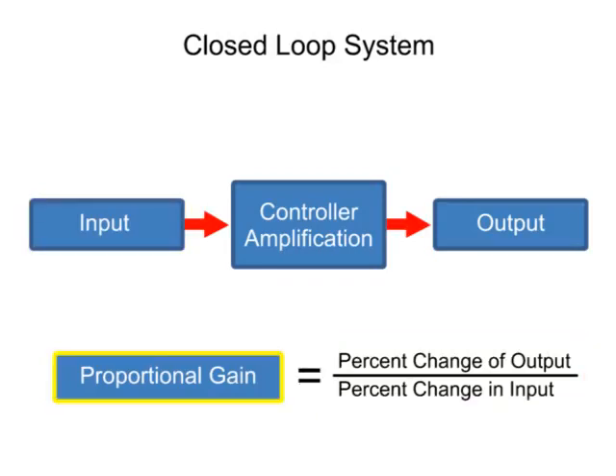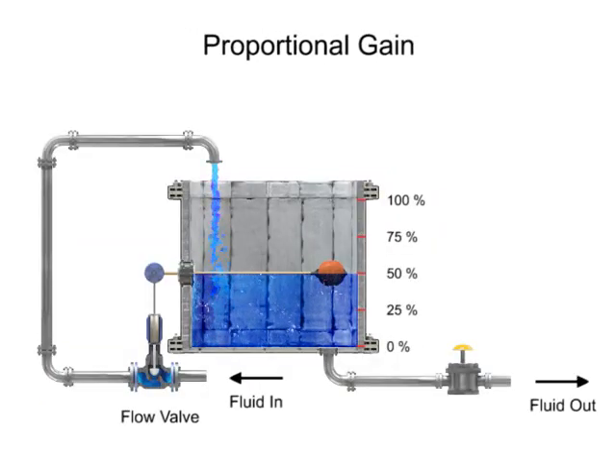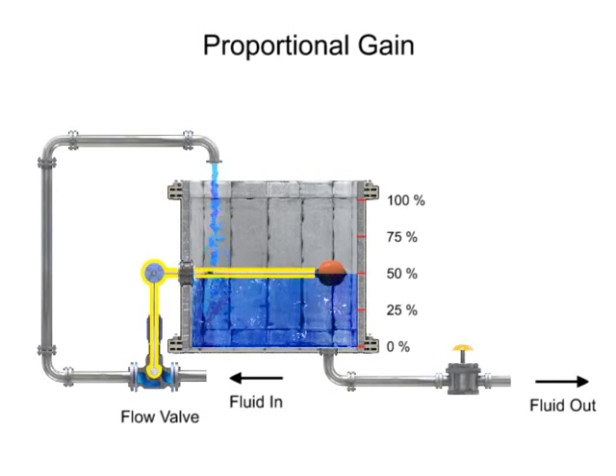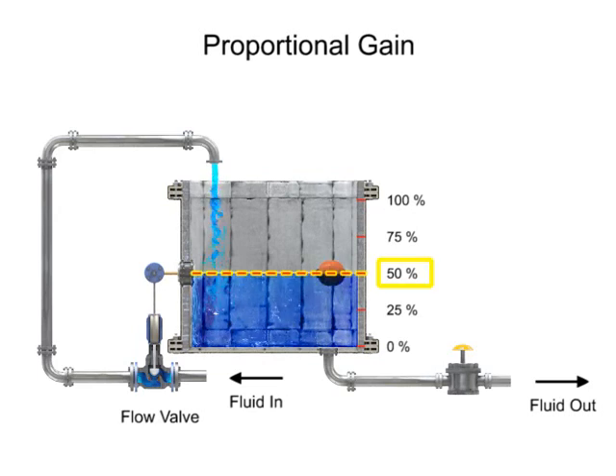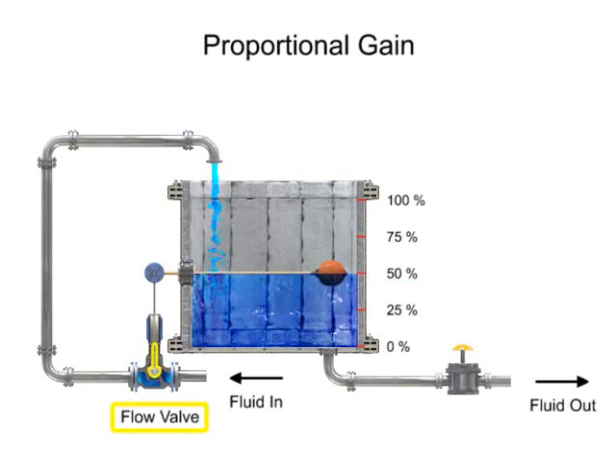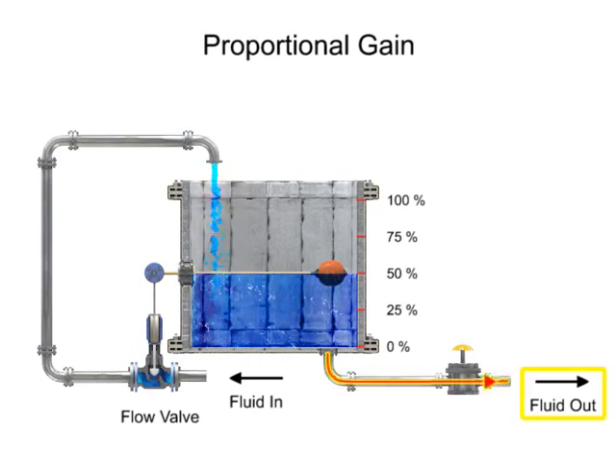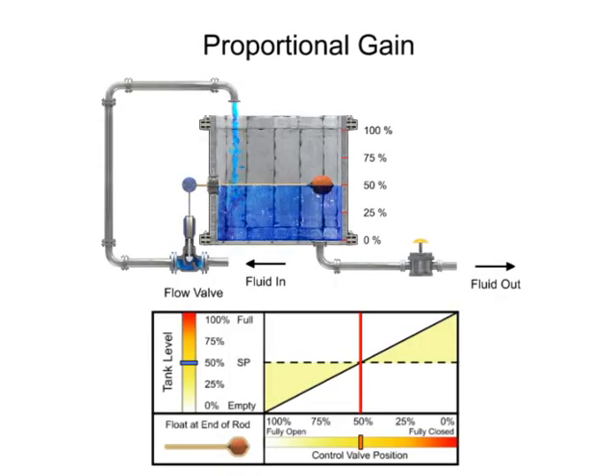To illustrate the concept of gain, a common process of regulating the level of fluid in a tank with a float attached to a control valve is used. The float mechanism is designed so that when the tank level is half-full, the flow valve is open to the position that causes the amount of fluid entering the tank to equal the amount leaving. The float on the end of the rod is positioned to meet the minimum and maximum flow capability of the valve.